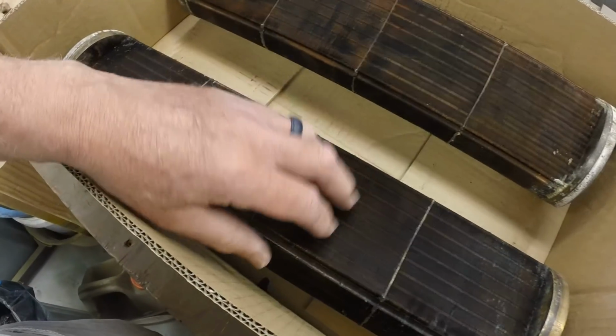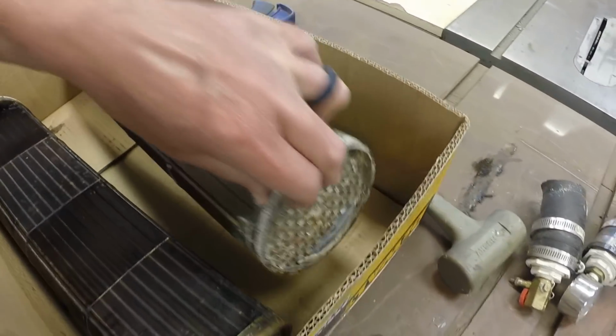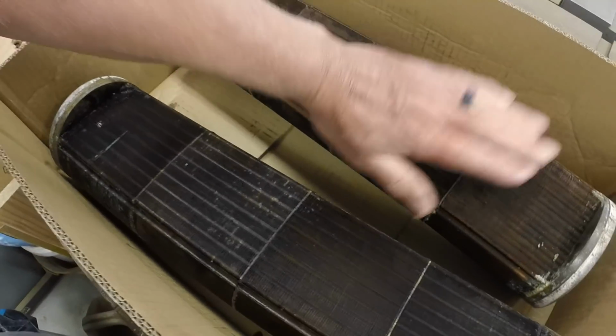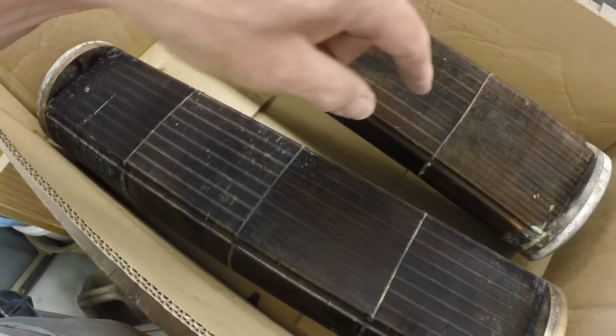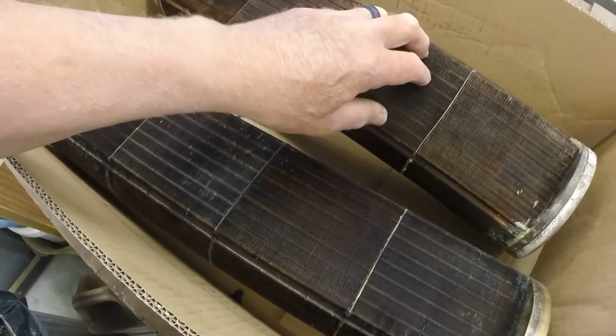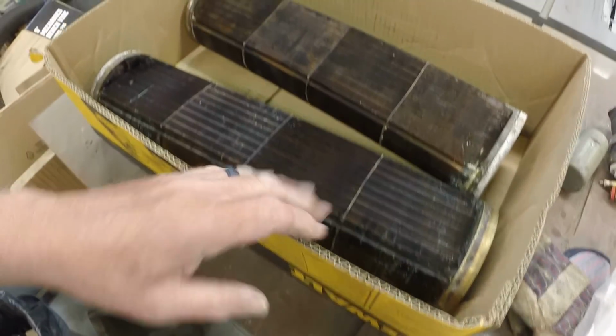So these are the cores. Seawater flows through the tubes, air blows across and through the core, and the purpose of the aftercooler is to take the hot compressed air coming from the turbo and cool it down so you can increase the air charge in the cylinders, get more horsepower, and burn more fuel.